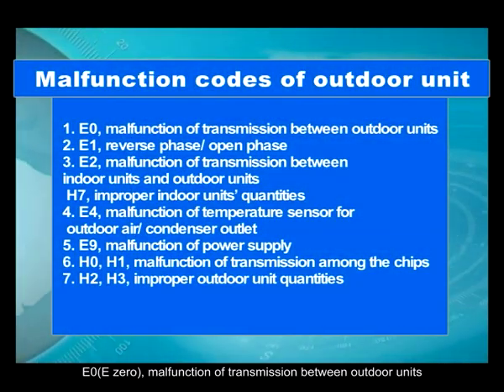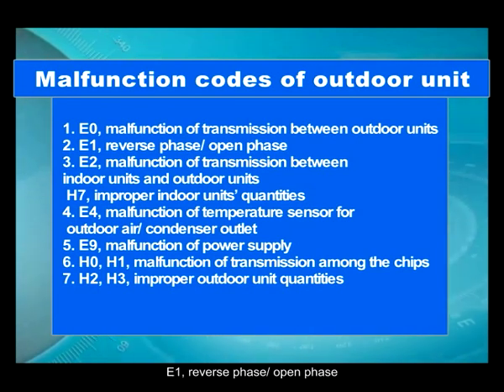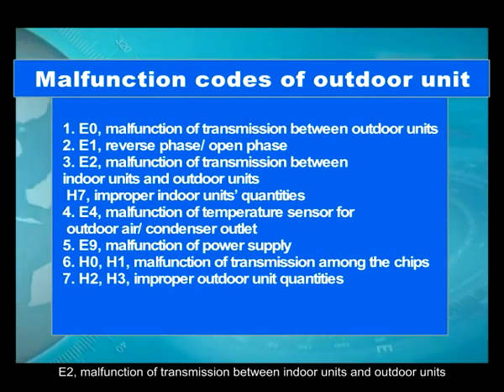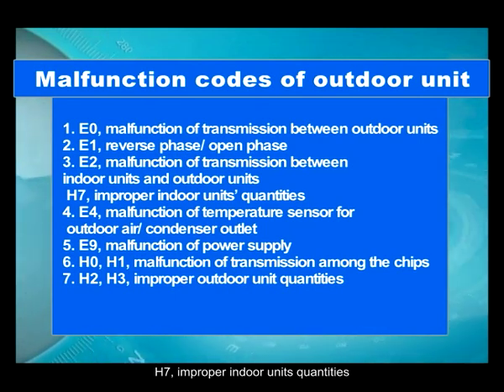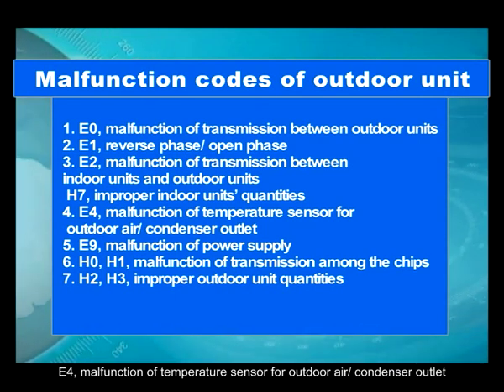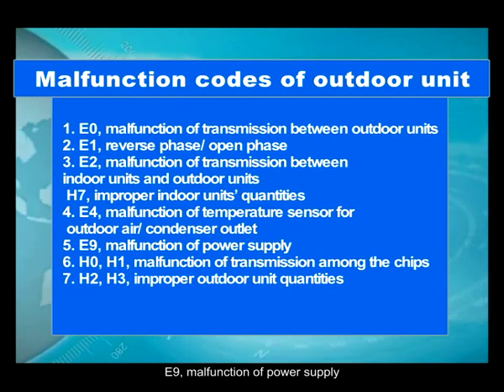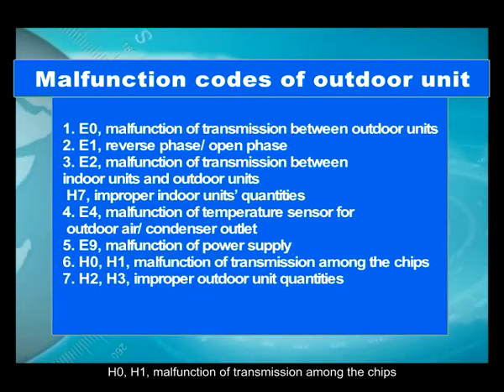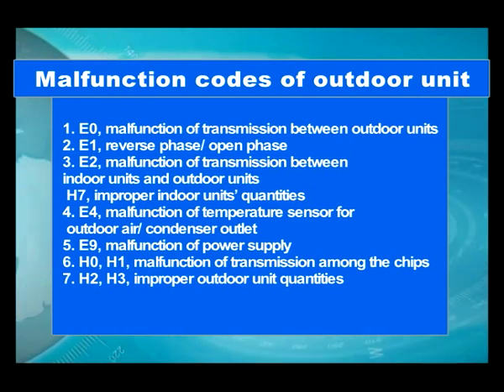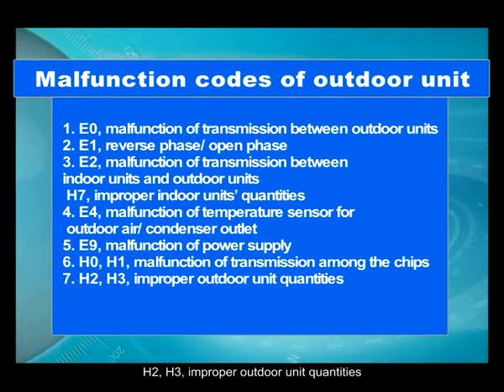E0. Malfunction of transmission between outdoor units. E1. Reverse phase/open phase. E2. Malfunction of transmission between indoor units and outdoor units. H7. Improper indoor units quantity. E4. Malfunction of temperature sensor for outdoor air/condenser outlet. E9. Malfunction of power supply. H0, H1. Malfunction of transmission among the chips. H2, H3. Improper outdoor unit quantities.